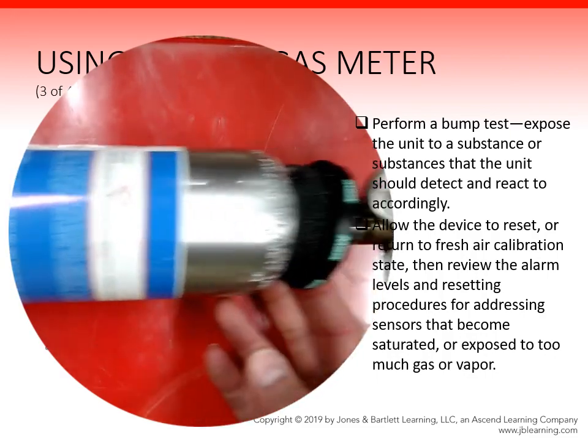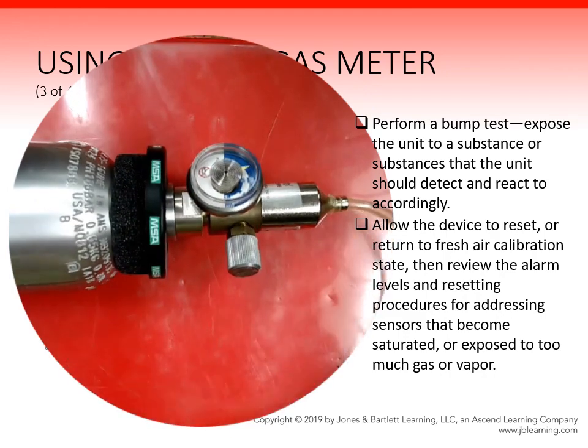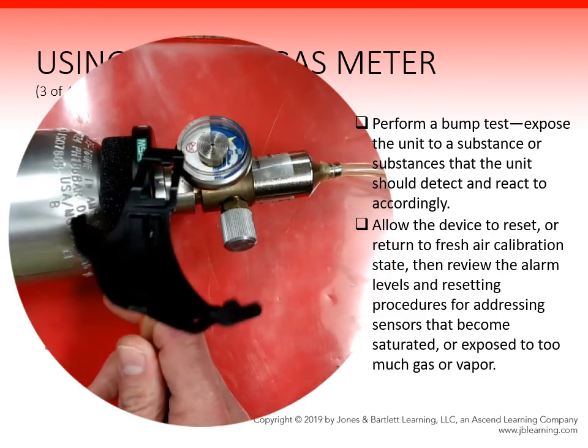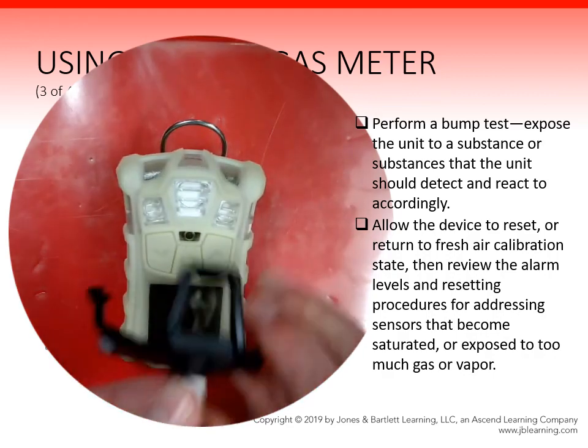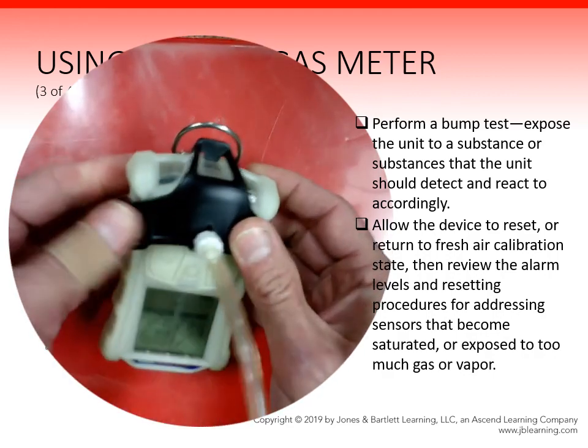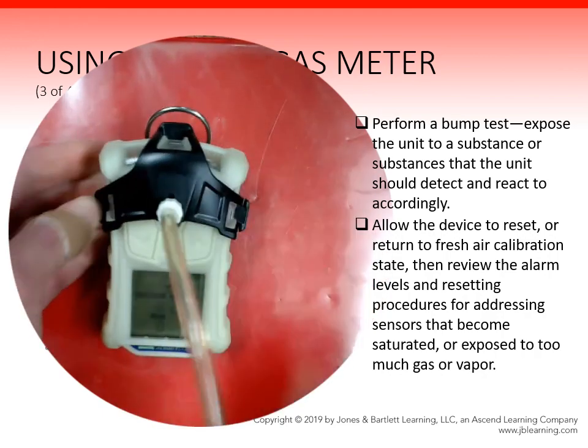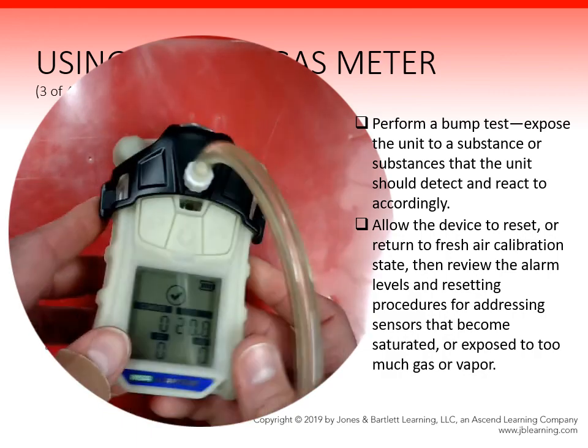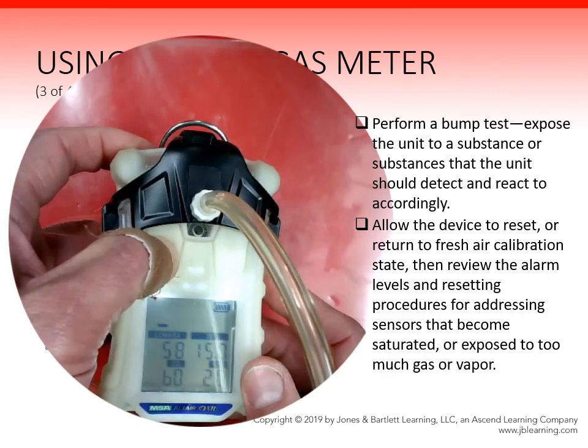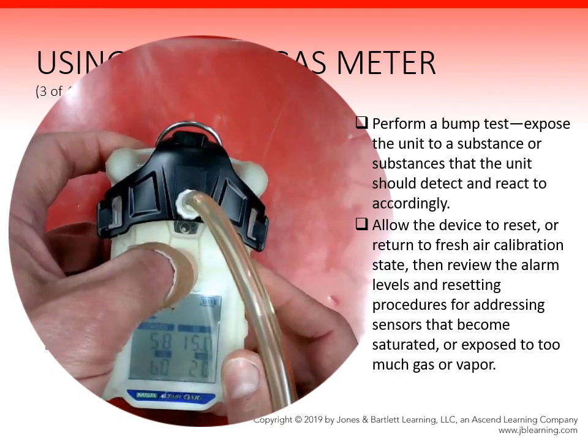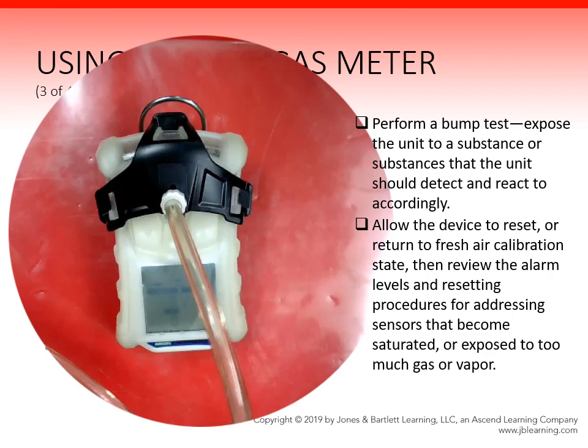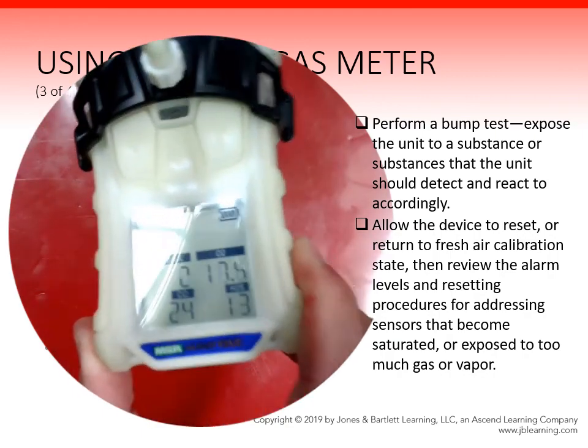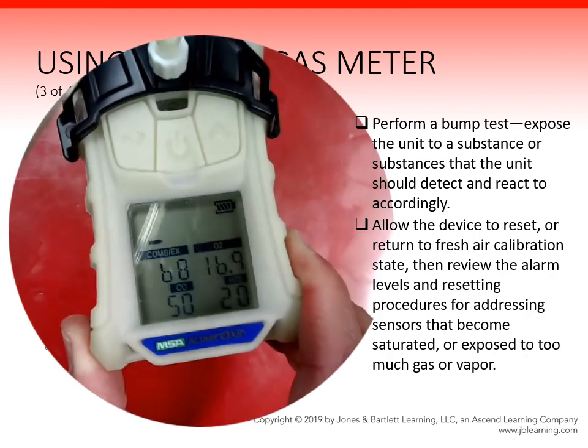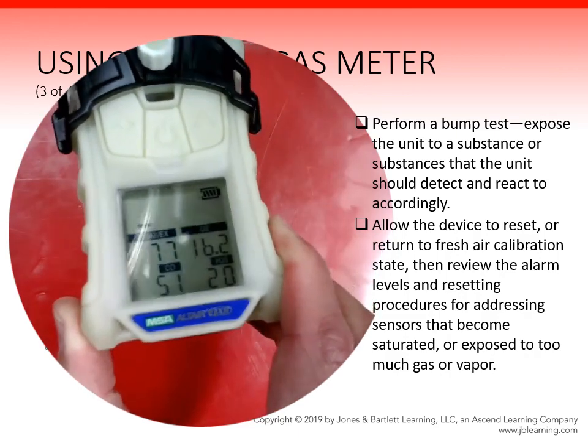So you can see the canister of gas there. It's got a regulator on there along with the tube, and then it's got the harness which attaches it to the meter. So I'm going to go ahead and attach that harness by snapping it down on the sides to the meter. You can hear it snap into place. I'm going to trigger the bump test by holding the down arrow key. It'll offer to give me a bump test, and I'll hit that power button in order to trigger that bump test to begin. I'm going to turn the gas on, and you'll see the values on that screen change as it detects the gas that's been calibrated for that bump test.